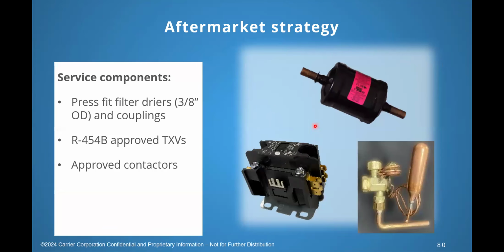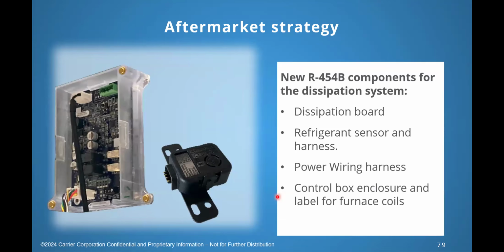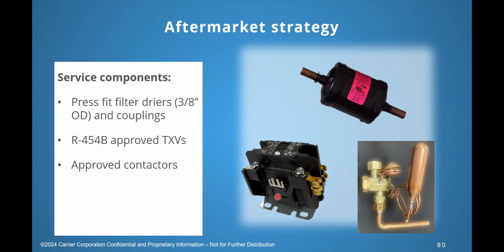And you're going to need to have A2L listed contactors. You cannot put a regular contactor into an A2L system. I mean, you could do it, like electrically it would work, but it's not allowed. The new A2L contactors are more enclosed. They can be spark proof, if you will. So you have to have an A2L contactor. You could put an A2L contactor on a regular A1 system, but I don't know why you would do that. But so you guys are going to need contactors, sensors, and leak boards.